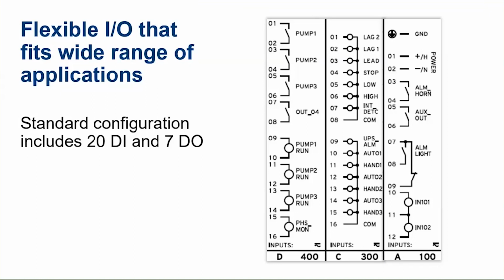Let's talk about that pump card in slot D, as in dog. You see that there are outputs at the top for pump 1, pump 2, pump 3. Those are high current outputs. They can make 30 amps, break 10 amps, and carry up to 4 amps continuously. That allows you to do a lot with those outputs without having to have interposing relays in place in your panel, which eliminates that other point of failure. All of the digital inputs are optically isolated, which allows you to not have to worry so much about transients from lightning strikes or power fluctuations taking out some of your inputs.